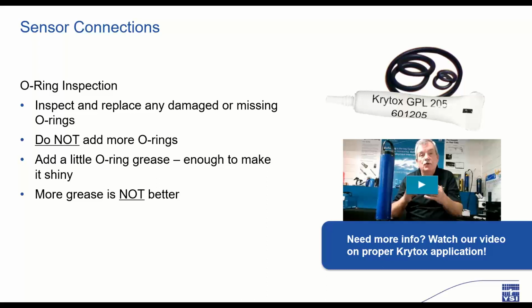If the O-rings are in good shape, then a simple cleaning and relubricating will help ensure that your equipment is protected against moisture intrusion. Make sure to inspect the O-rings on your sensors, sondes, and battery compartment seals on your handheld. Replace any that are damaged or missing to prevent water or dirt intrusion. And if you're new to the field of sampling, these O-rings are the little, usually black rubber rings that you may see in different places on your instrumentation. Never add more O-rings in an attempt to make the seal better. That isn't how O-rings work, and you can actually promote leakage by doing this.